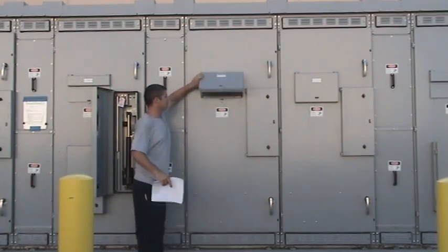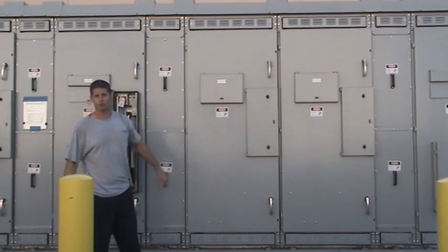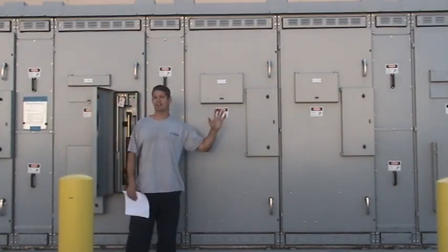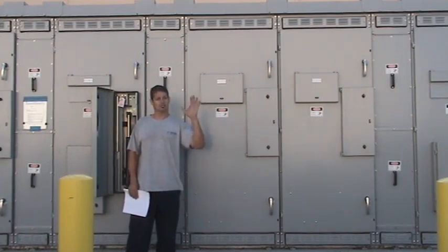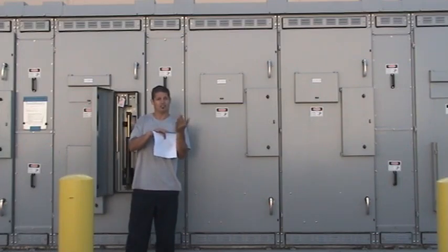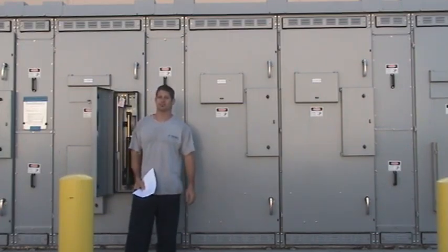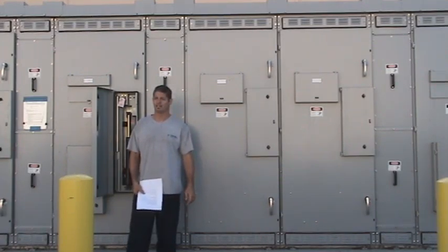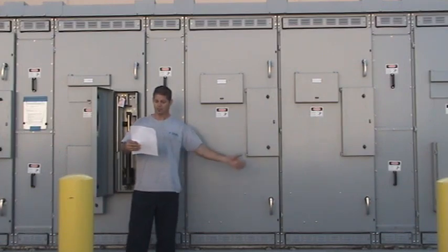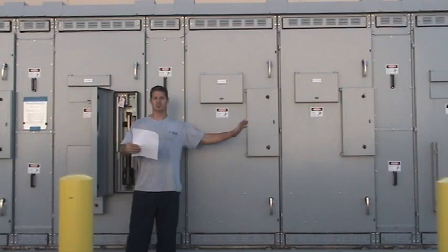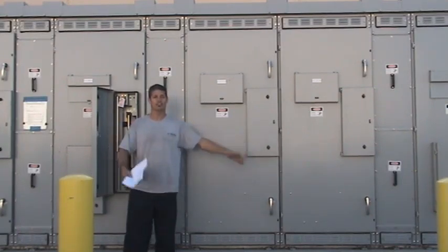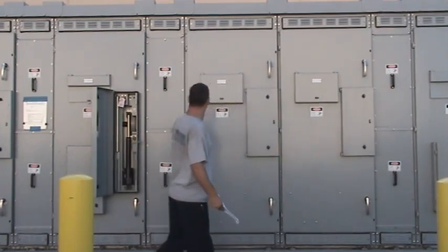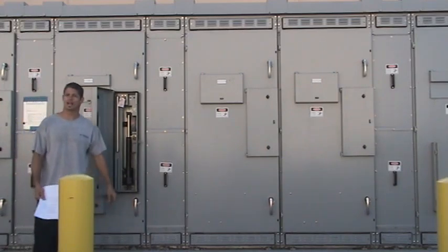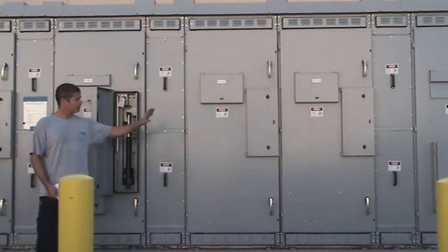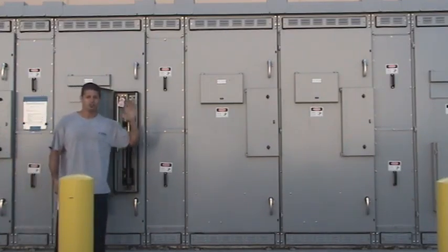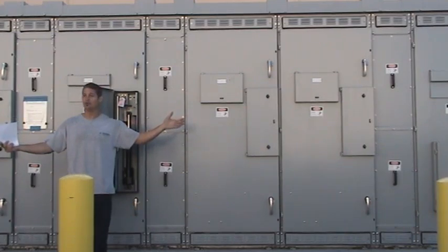In here you'll see the blades of all the switches. Every one has a window. If the switches are failing at any point, you'll be able to tell by some arcing on the blades themselves. So a standard visual inspection on this would probably want to be put into your maintenance routine. The only other thing on these switchgears that possibly could be a maintenance issue is the fuses. Every single one of them inside is fused all the way across, and I've provided spare fuses to Randy per the specification, so you have a spare fuse for every one in here, and you'll know when they go out. It's going to tell you when they go out.